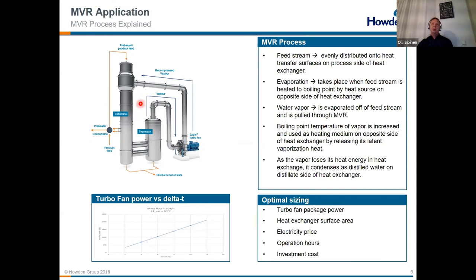decided by what the electricity price is there, and what the capital investment of this kind of a system is there. So if we are evaporating some exotic things, these calandrias or heat exchangers could be, for example, titanium, which is a very expensive component, and then the higher delta T could be needed, or vice versa, if you have some seasonal product there, when you want to have a low capex and then the higher opex is accepted. So there are different parameters that the process EPC and our clients are playing with when they're selecting the evaporation system.